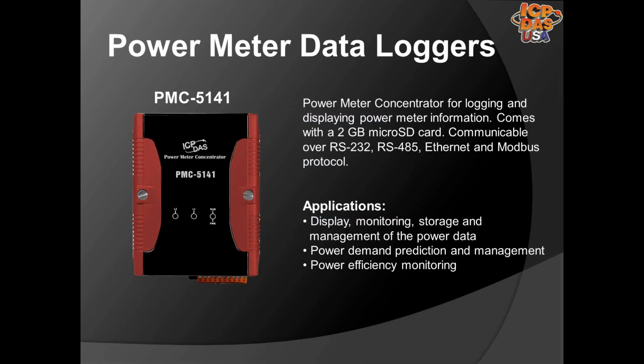They can log data from Modbus RTU devices and can communicate back to SCADA or other systems over Modbus TCP protocol. With power meter data loggers, you can predict power demands and manage and store power data. You can create different users that can log in through a web page to see the data, and different users can have different permission levels. It has 2 Ethernet ports and a Windows CE operating system.